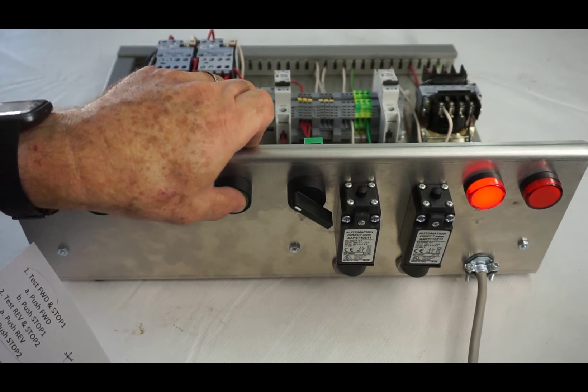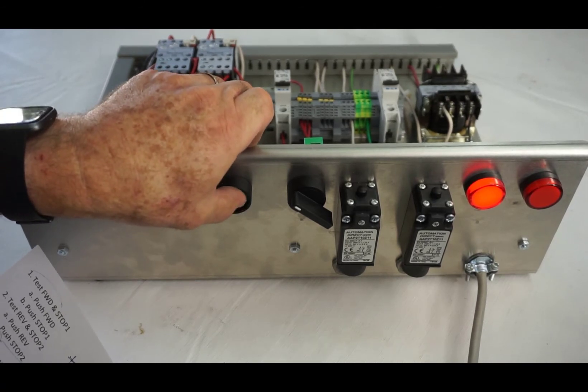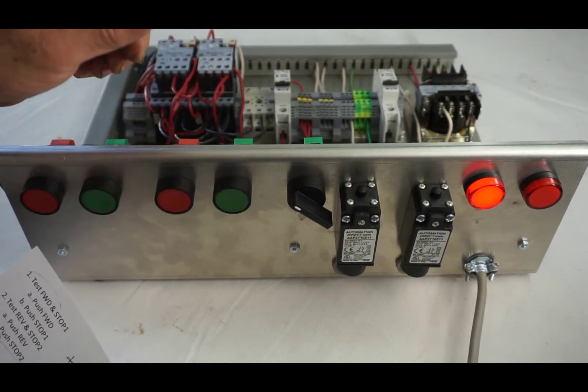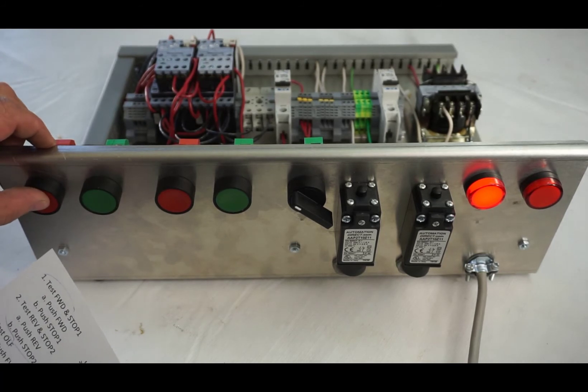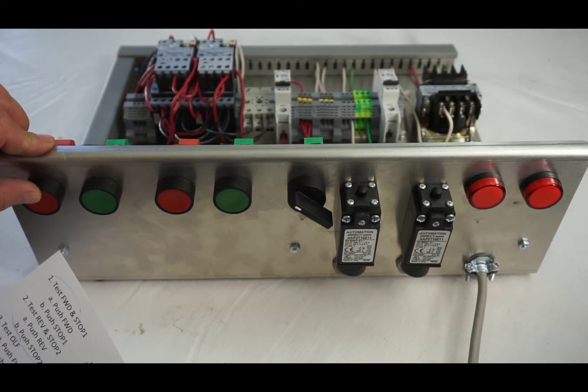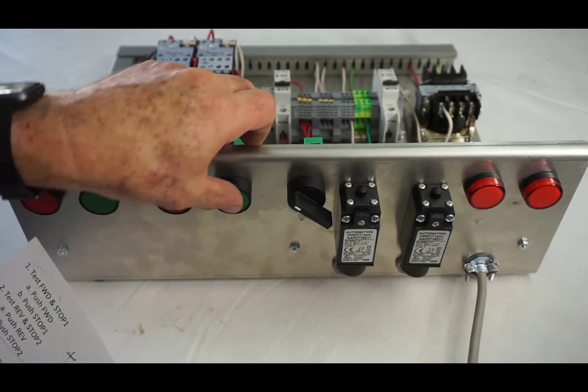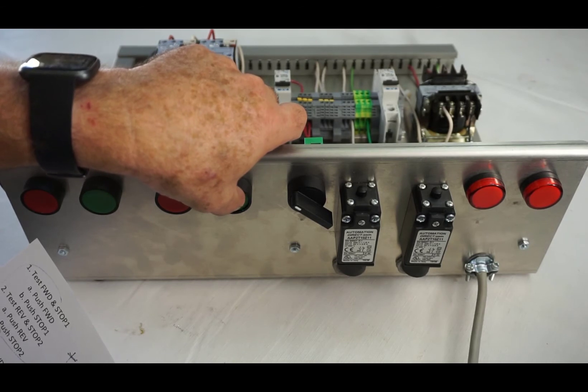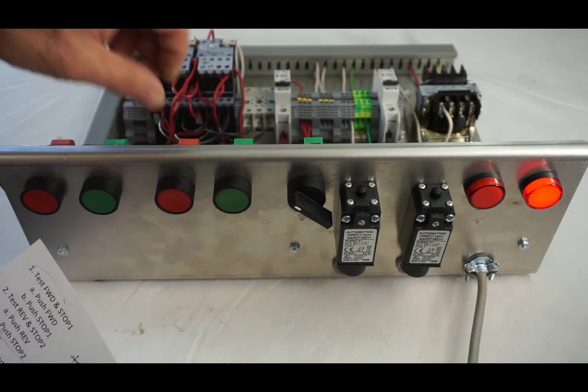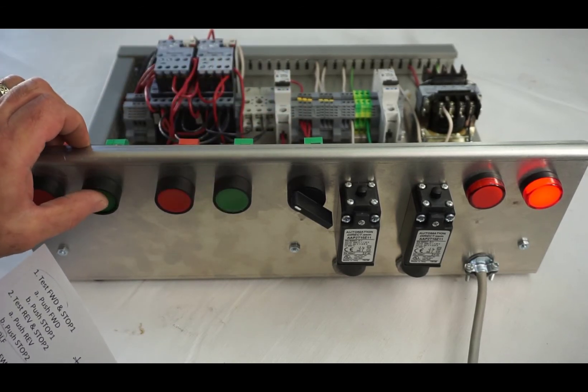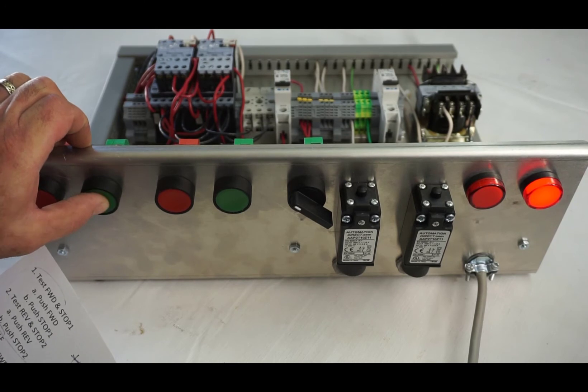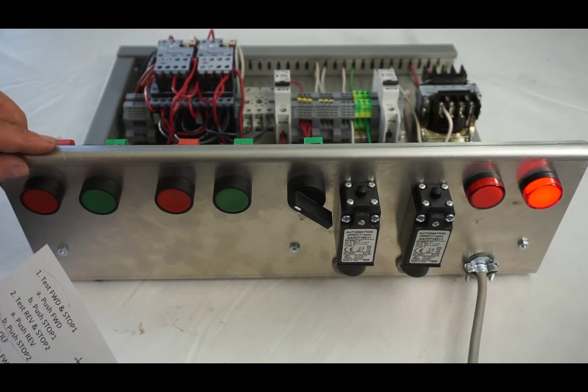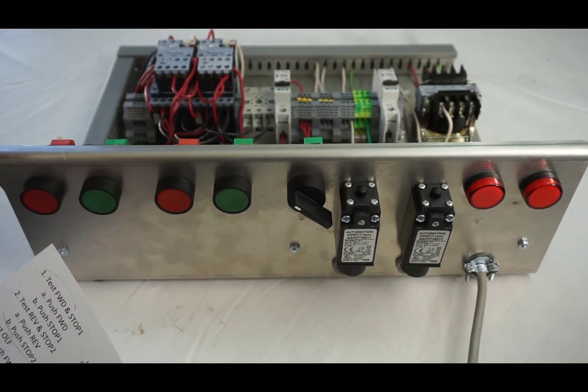Push stop one. Okay, reverse interlocks. Again, we'll push reverse. I'm going to listen. Nothing, okay, so we're good there and we're going to stop.